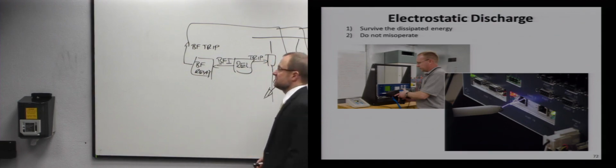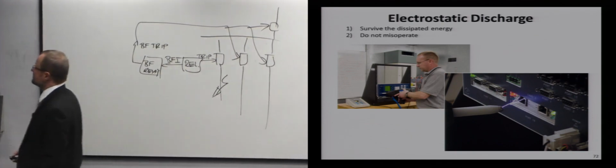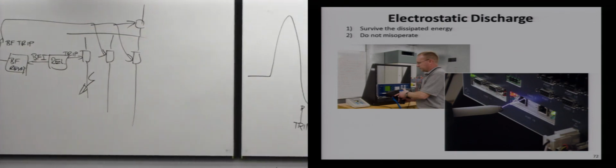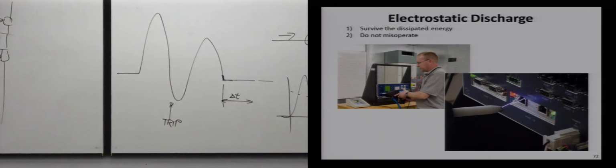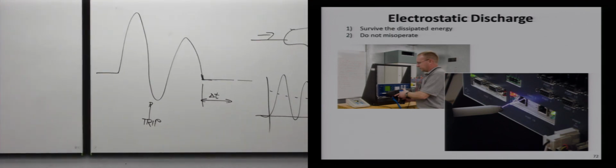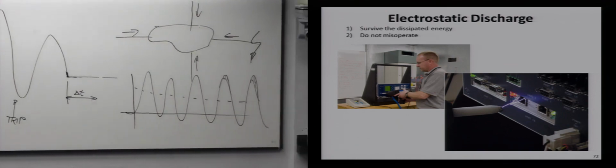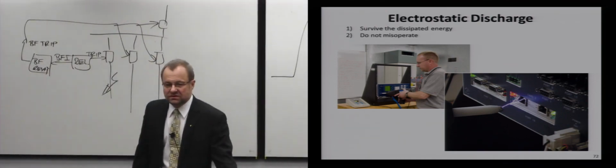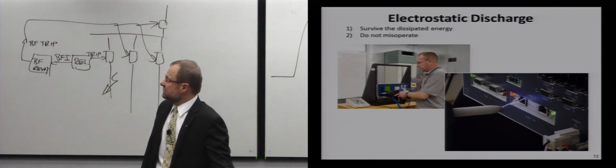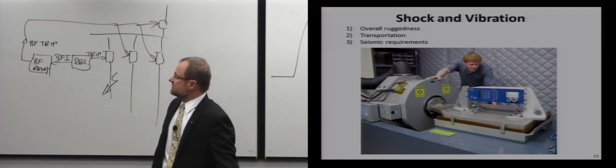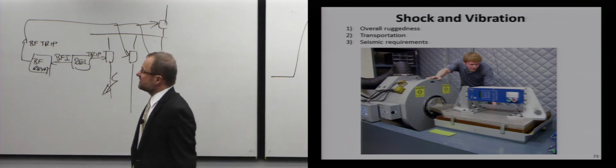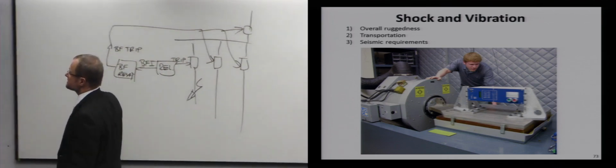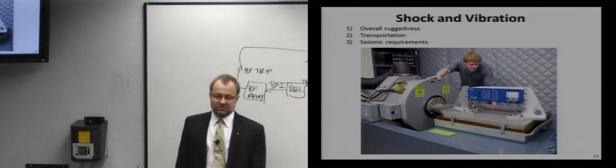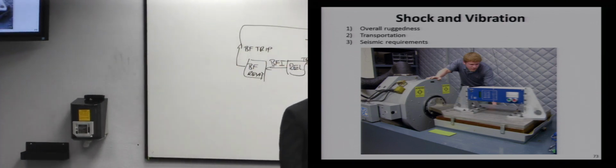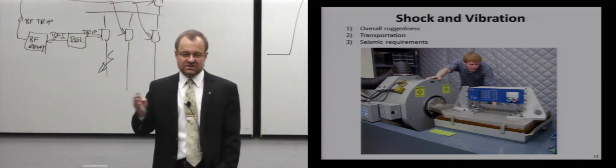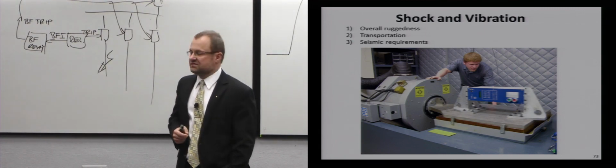Electrostatic discharge, especially for ports: there are humans there, we walk, we wear clothes, so we could bring electricity to those connectors. So you have to shoot them with certain energy levels, and the thing should not only survive, it should not reboot, it should not trip the breaker, because things happen. This is the other fun that we have. You may think that this picture is not in focus, and partially it's true. The reason that relay is not in focus is because it's vibrating. This is a vibration test where you basically stress the device for vibration.